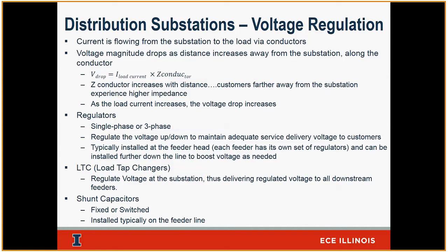So if I live at the end of the line here, because of this voltage drop, let's say this is my boundary, and I come out of the substation at, say, 120 volts. As I go down here, because of this voltage drop, this customer might be seeing 114 or 115, whatever voltage he's got. I want to make sure that this customer is not going to see a violation. So I'm going to regulate the voltage. I can bring it up or down depending on my impedance, depending on my load.